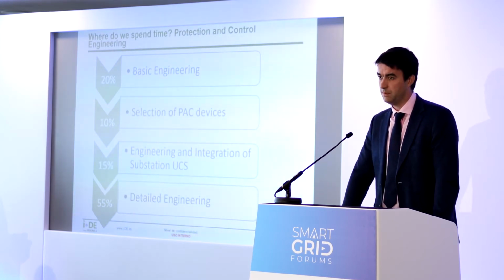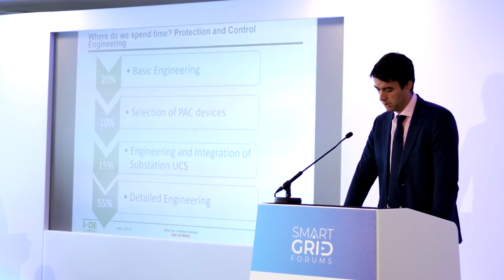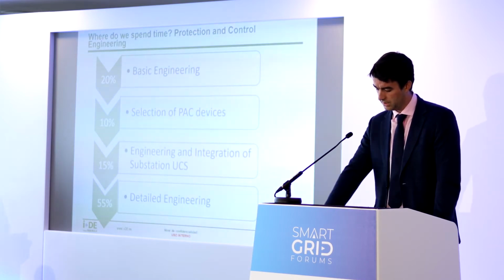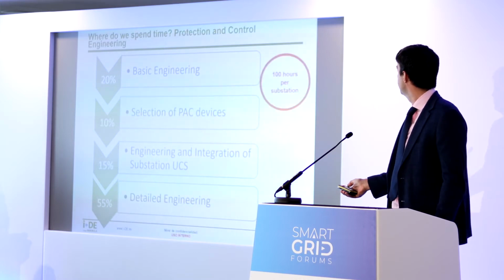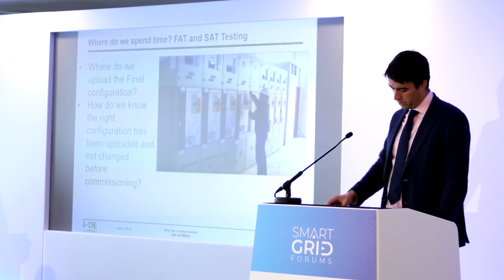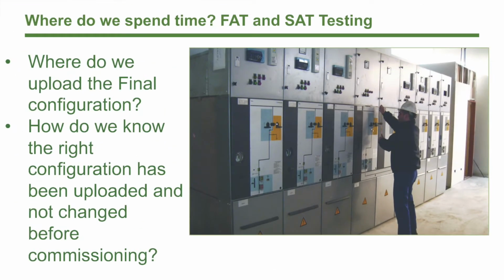So a lot of time is spent on device testing, because although we have long recognized that the switchgear manufacturer who is responsible for installing the IED is much faster and resolves problems much quicker during the factory acceptance tests than we could do with the site acceptance tests, we have never been able to optimize the FAT tests in such a way that we could be completely happy to reduce those SAT tests to an absolute minimum.